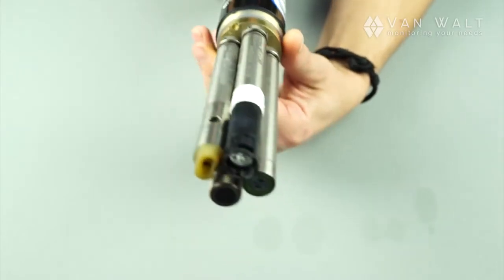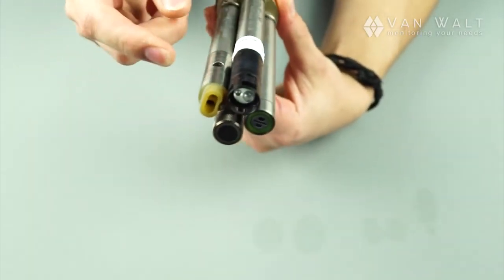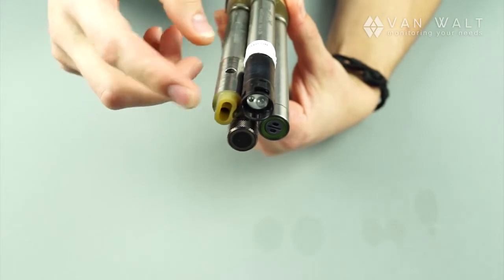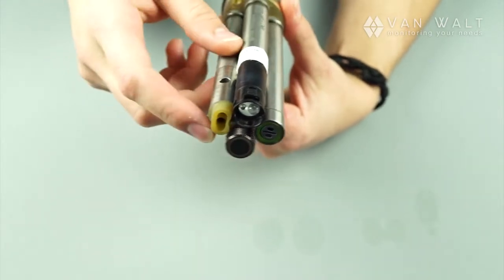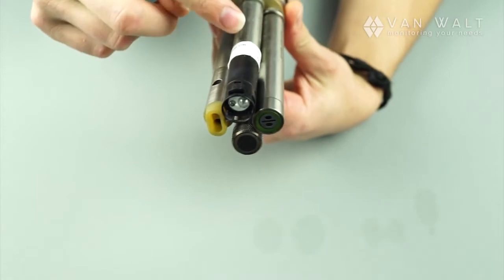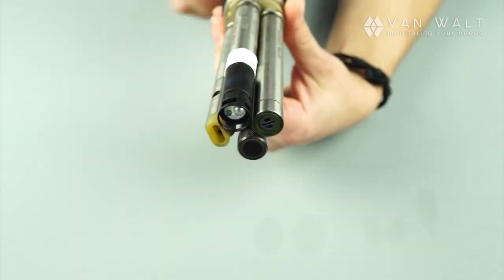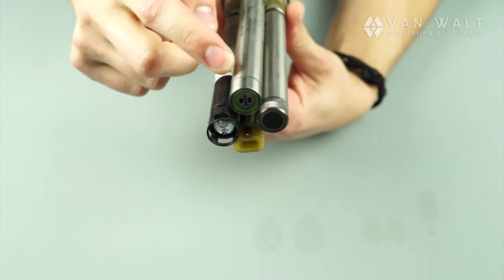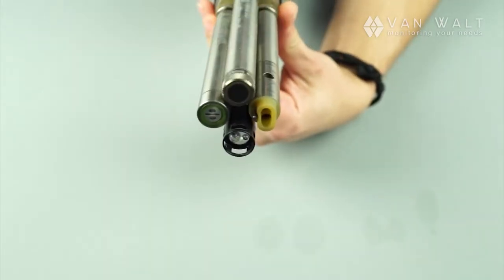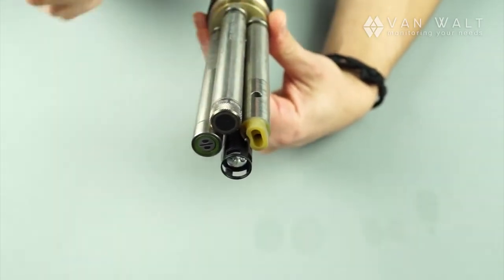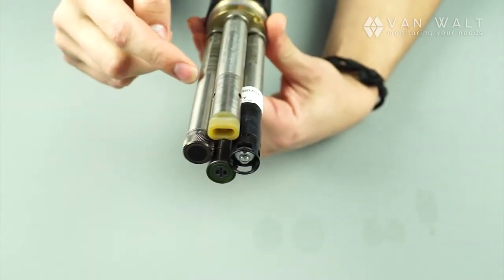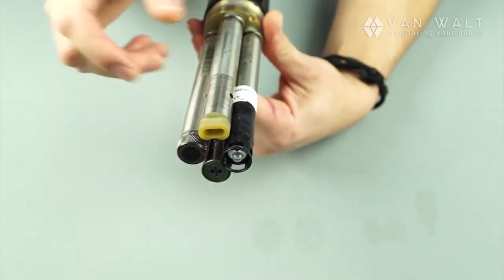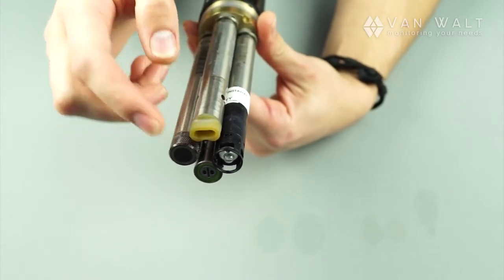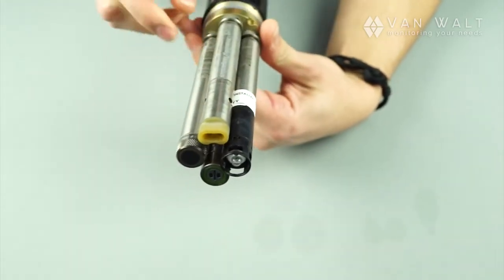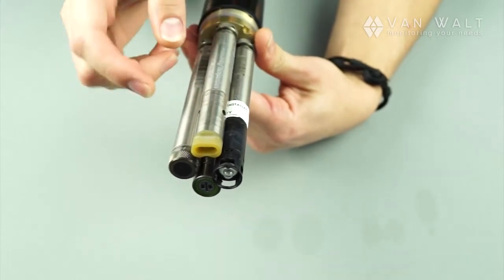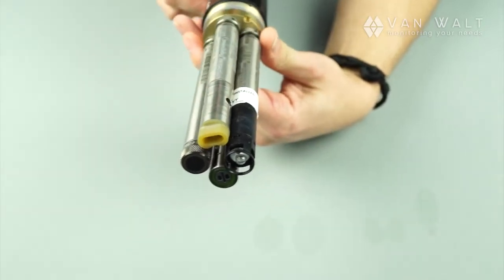So if we look at the probe end here, this probe on our right hand side is the conductivity and accurate temperature. This probe is obviously our pH and ORP combined. This probe is turbidity, and this is our optical DO probe. Each probe has a backup temperature unit internal, but this one is being used as our accurate temperature, and everyone will use this probe as its reference, even though there is a backup, again, just for reliability.